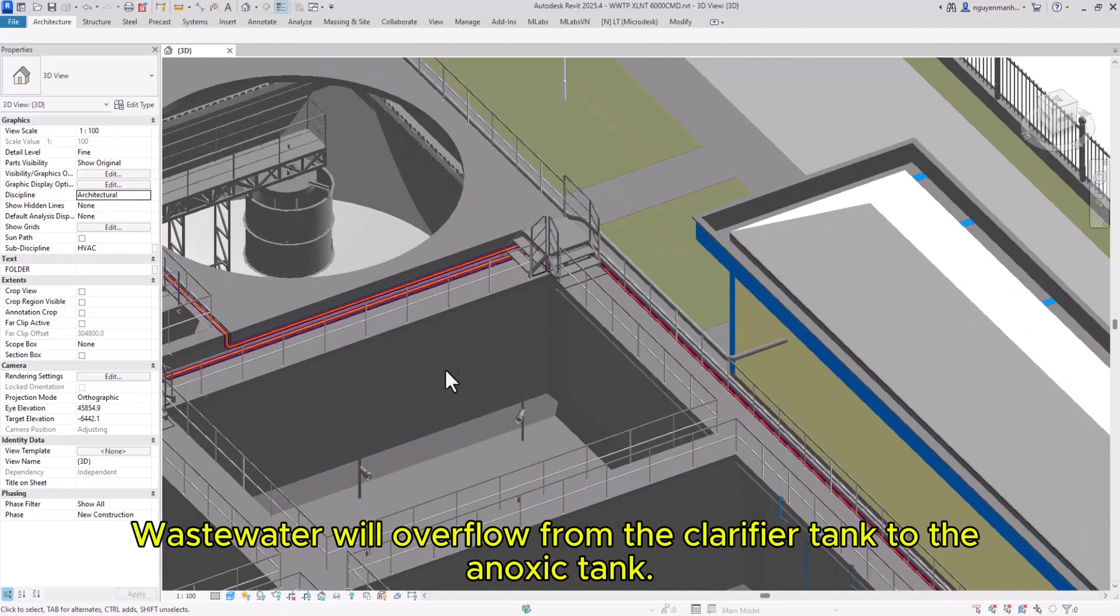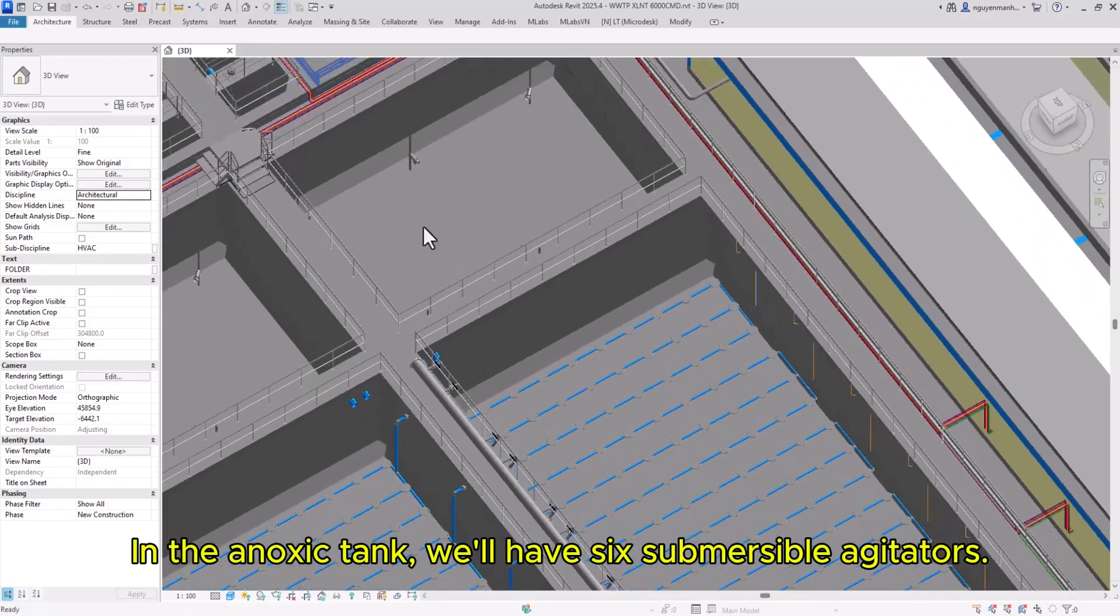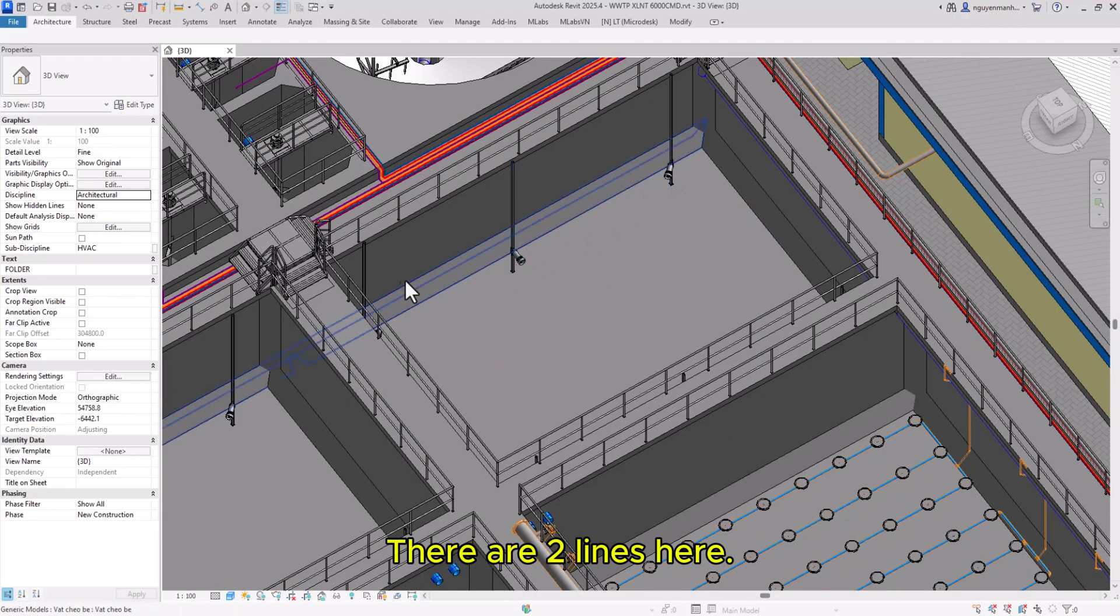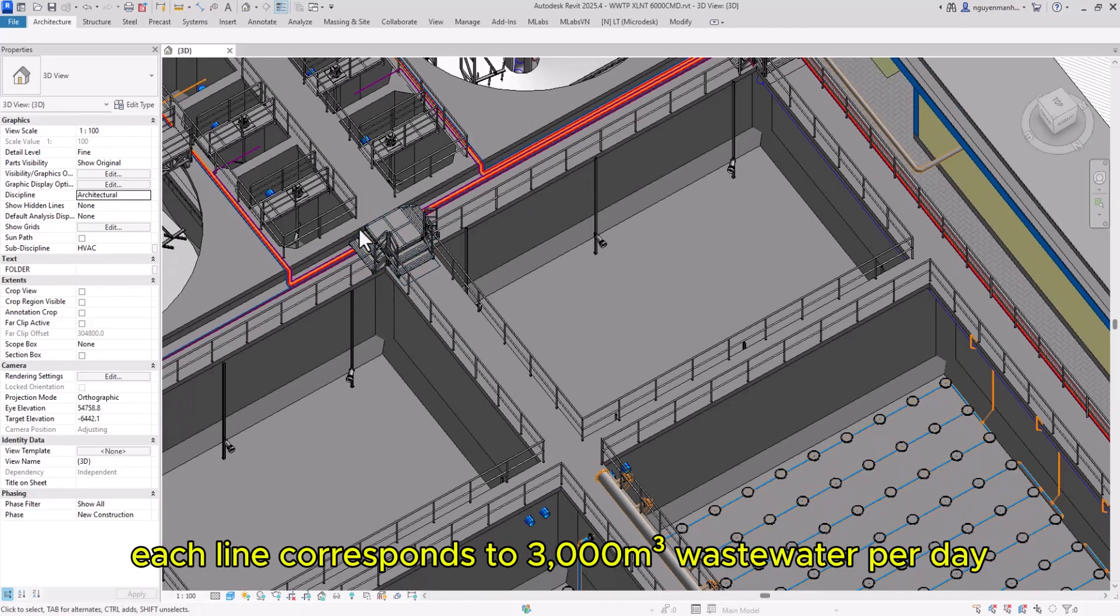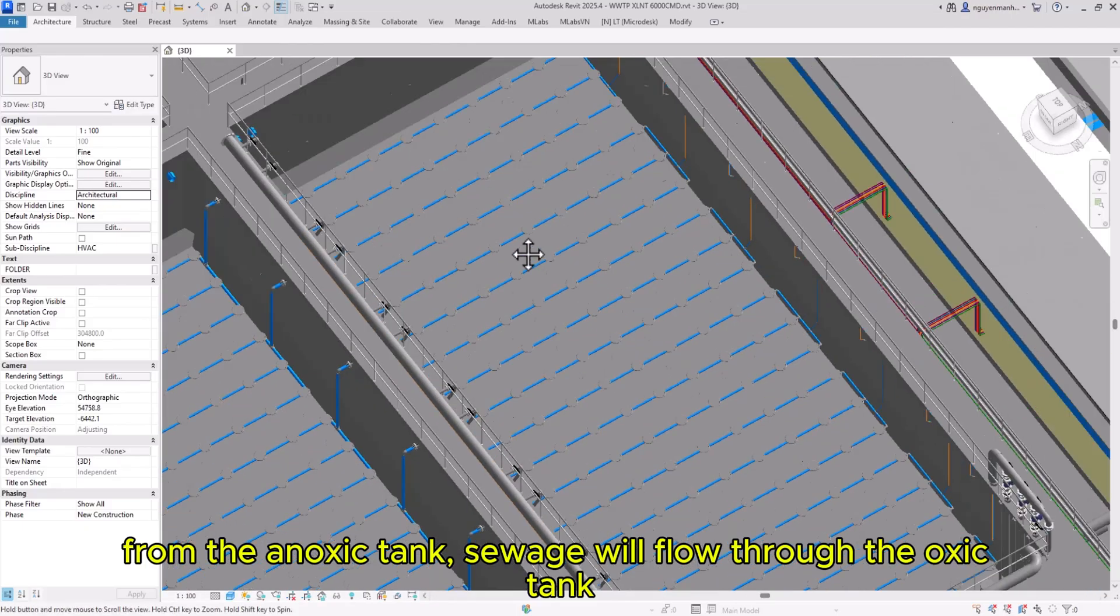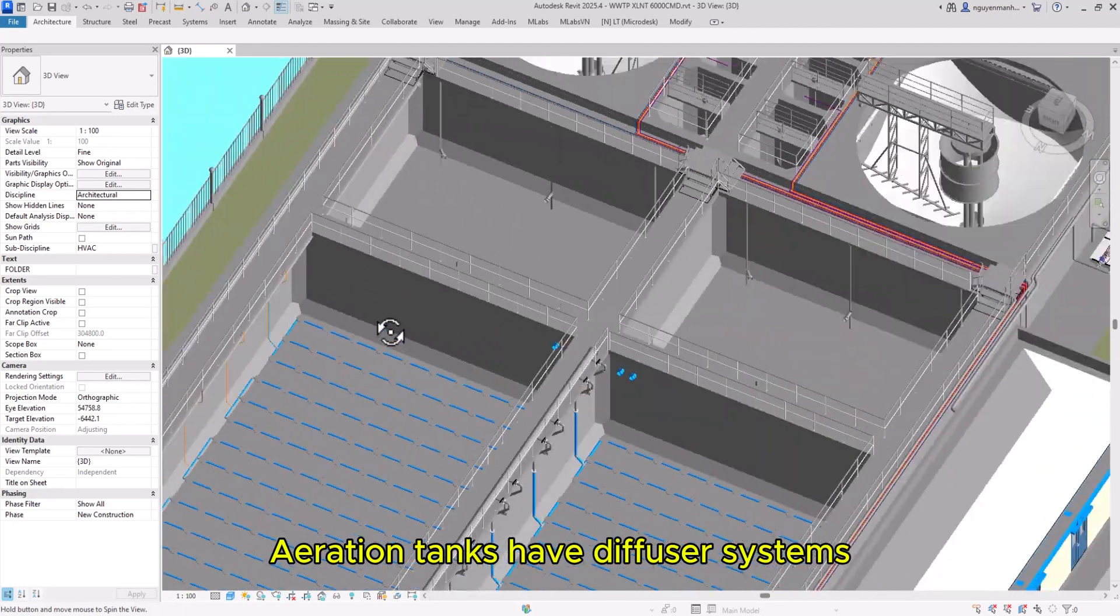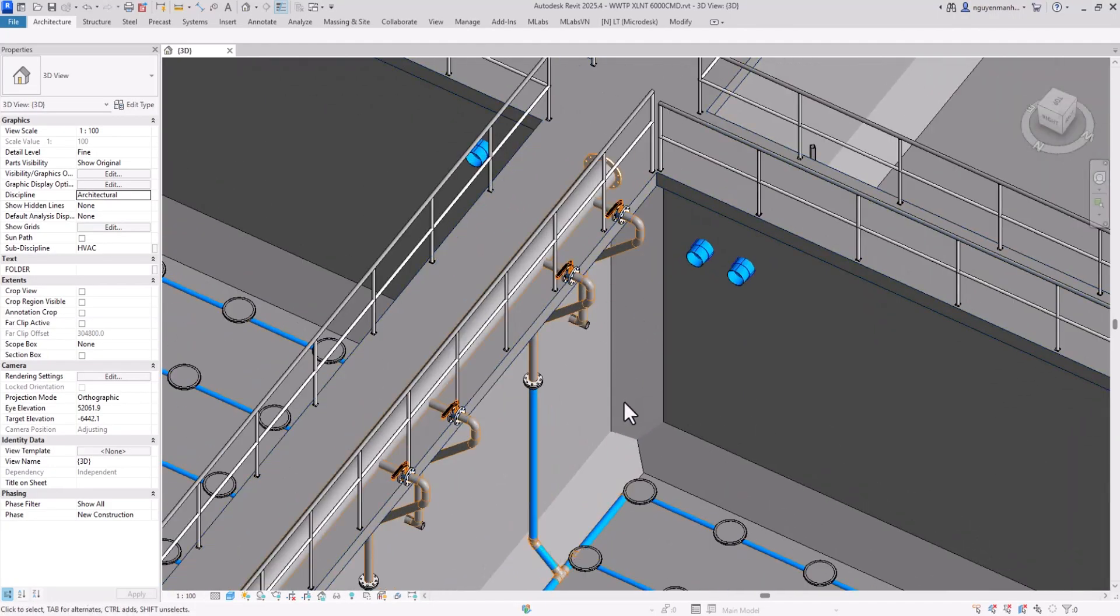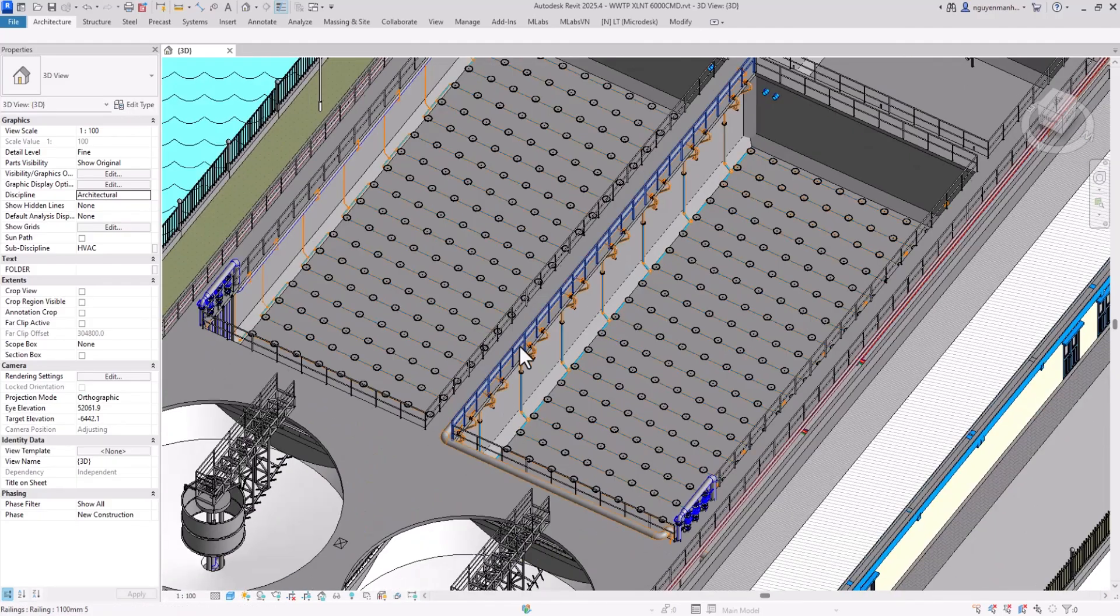Wastewater overflows from the clarifier tank to the anoxic tank. In the anoxic tank, there are six submersible agitators. There are two lines here, each corresponding to 3,000 cubic meters of wastewater per day. From the anoxic tank, sewage flows to the oxic tank. The aeration tanks have diffuser systems divided into many different modules with air ducts from the top down.